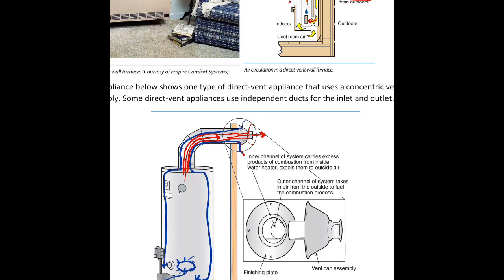That's your flame coming from the gas valve, and then all those hot gases are going up a center tube and making their way directly from there. All the heat's got to make its way up to here and on out. Now where you can get into trouble is if this is not installed correctly. I had a situation where the customer had removed this panel. They had removed this panel right in this little area.